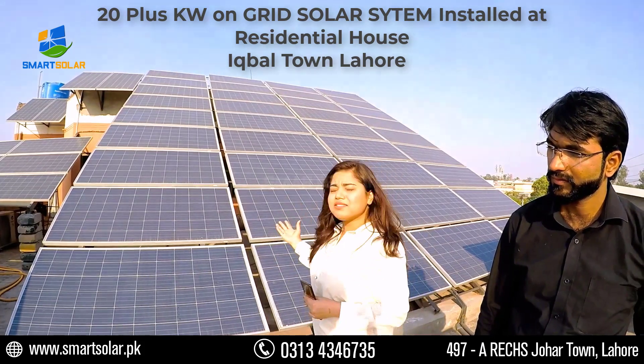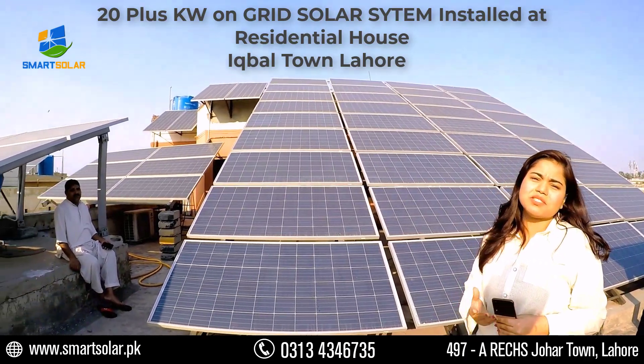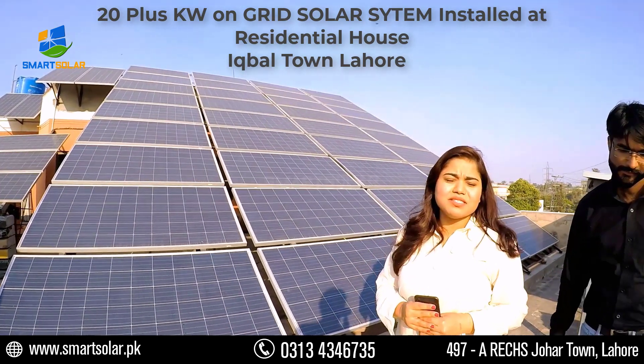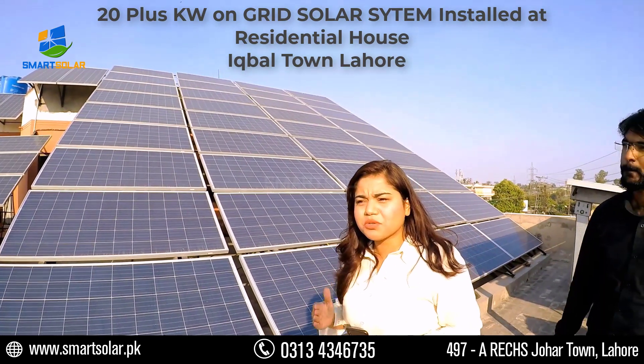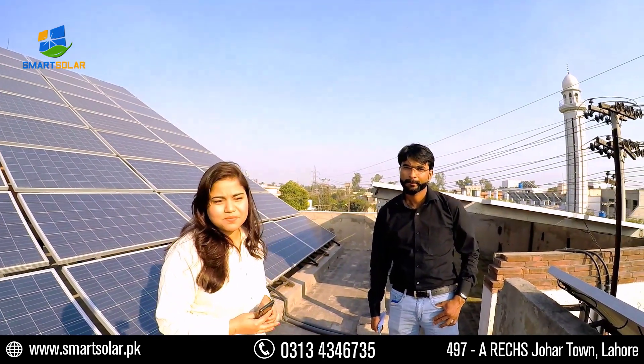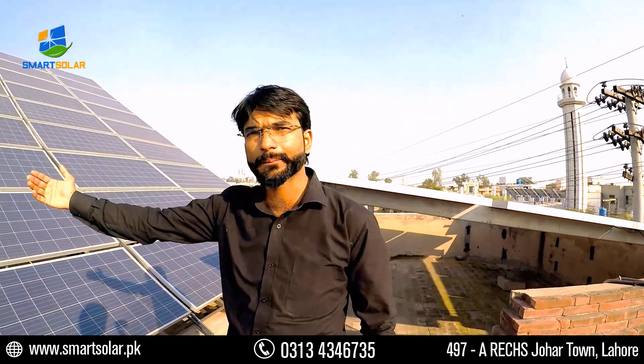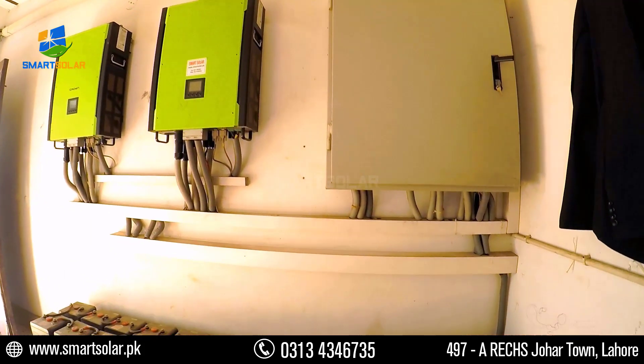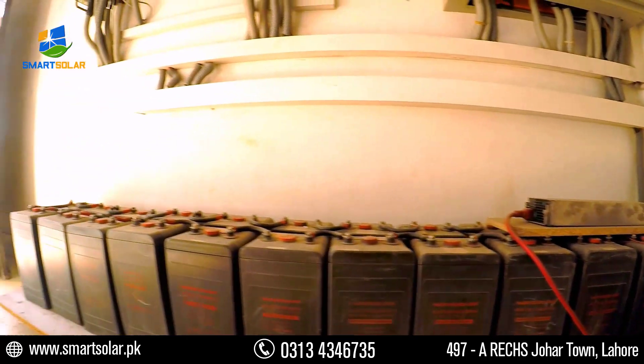Due to these panels, they produce 100-plus units on a daily basis. In this system they have made net metering — a grid meter on which surplus units are exported to the grid. They have also installed a battery bank with 2V 400Ah cells, so electricity is saved and utilized. During the day they use the solar energy and save the surplus to the grid.